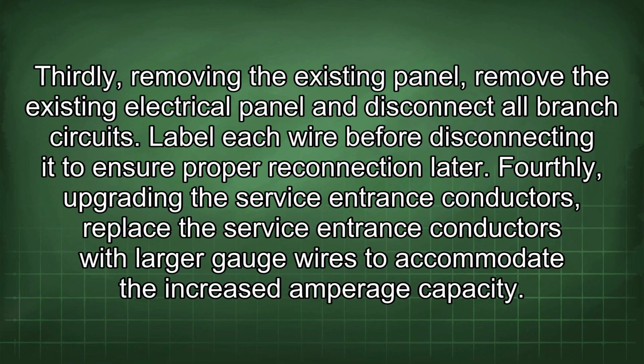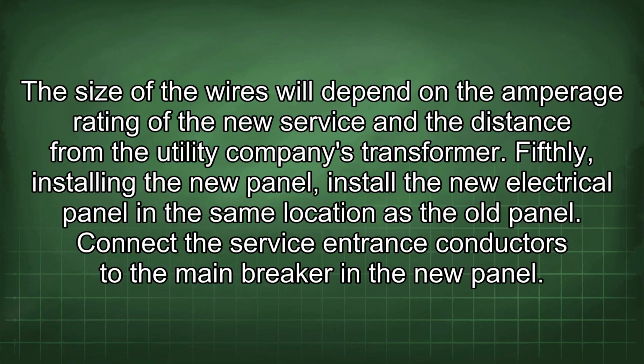Fourthly, upgrading the service entrance conductors. Replace the service entrance conductors with larger gauge wires to accommodate the increased amperage capacity. The size of the wires will depend on the amperage rating of the new service and the distance from the utility company's transformer. Fifthly, installing the new panel. Install the new electrical panel in the same location as the old panel. Connect the service entrance conductors to the main breaker in the new panel.